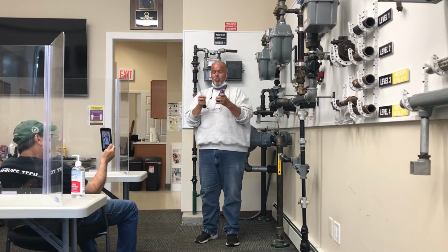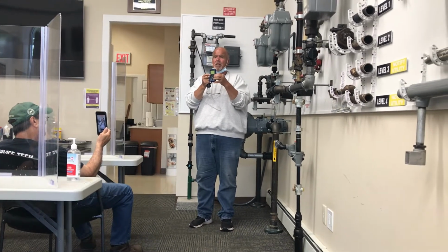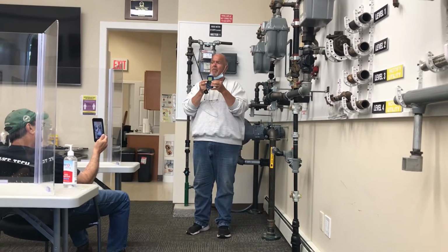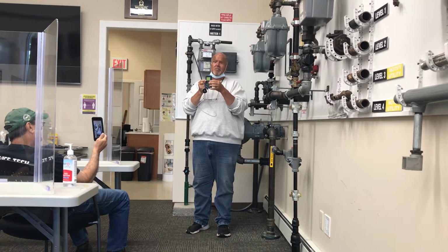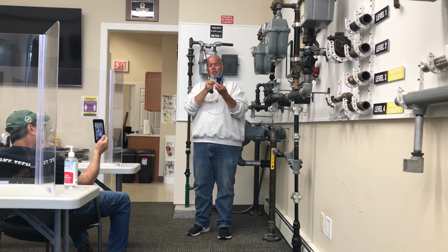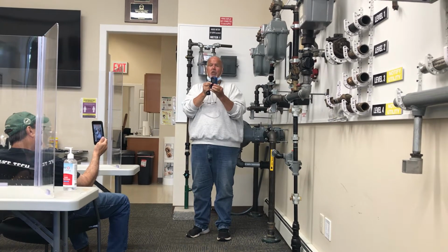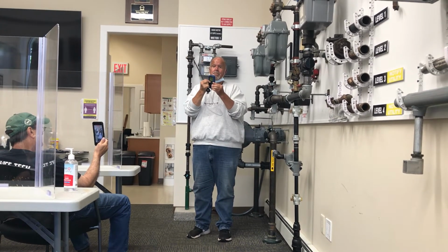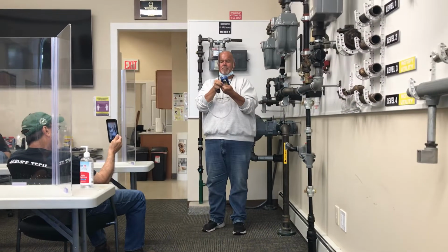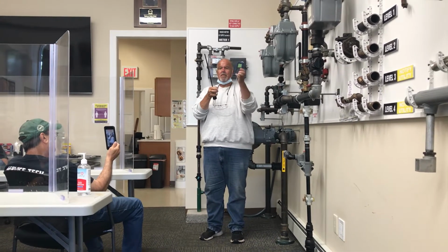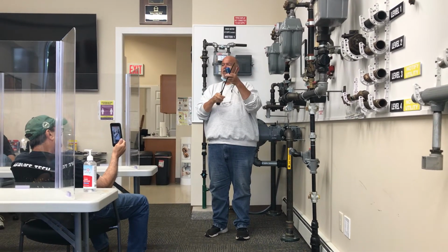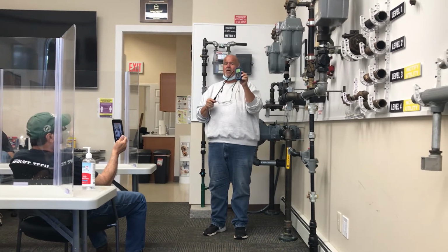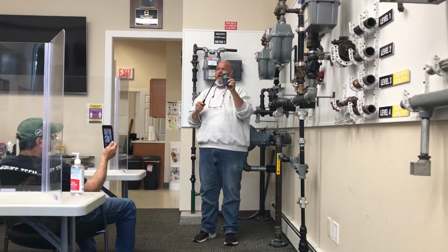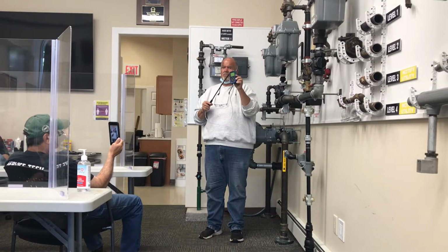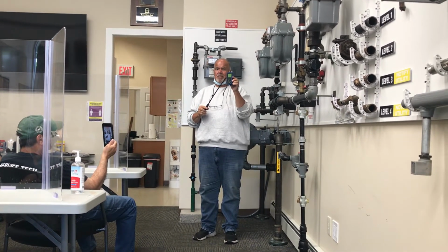To turn it on, there are 2 buttons on this PS200 LMP. There's a blue power button and a black mode button. To turn it on, you hold the blue power button down until the pump comes on. Let go of that button. The machine is now going to do a 30-second self-check. The first screen, you want to check for a full battery strength. Make sure you see 4 dots on that battery.